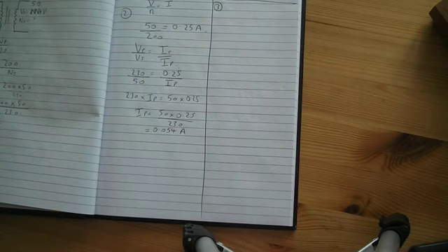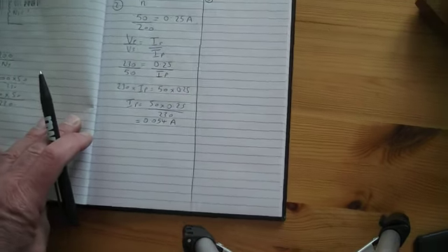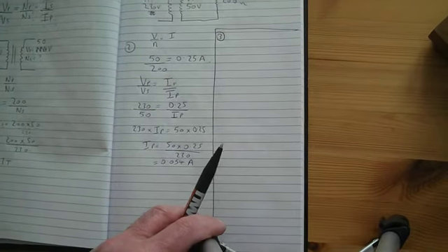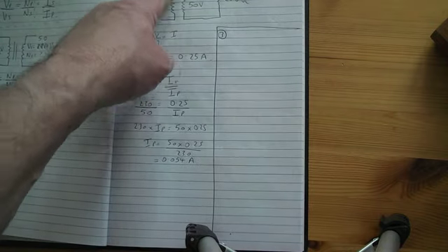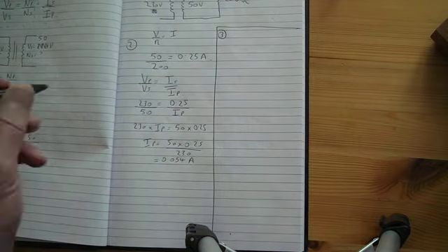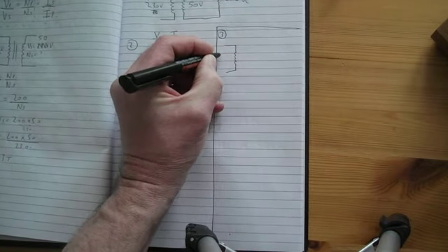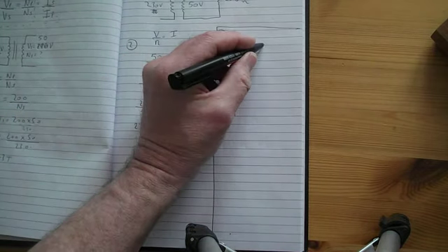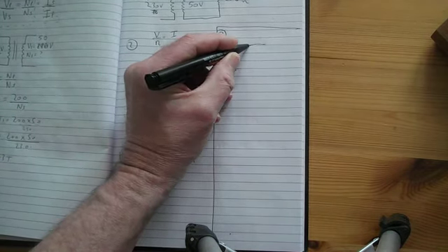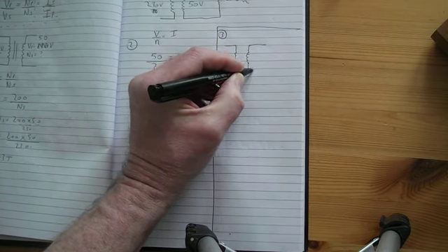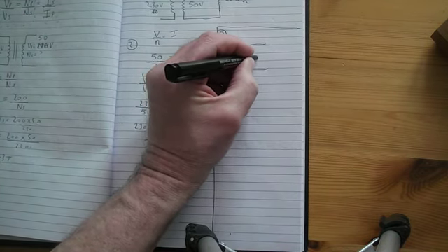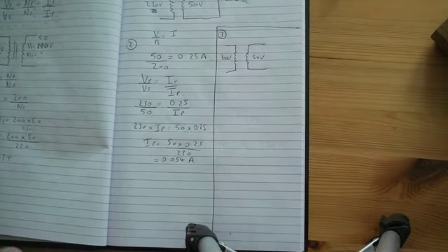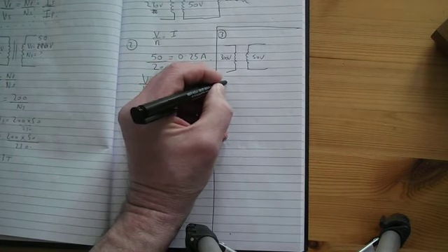Okay, right, now for the third part of the question. Now consider if we increase the voltage. If this voltage here accidentally rose to a higher voltage, say 300 volts, I want to keep this still at 50 volts. I have to reduce the number of turns on this secondary, and that's done often automatically in a transformer in your industry using a tap changer.